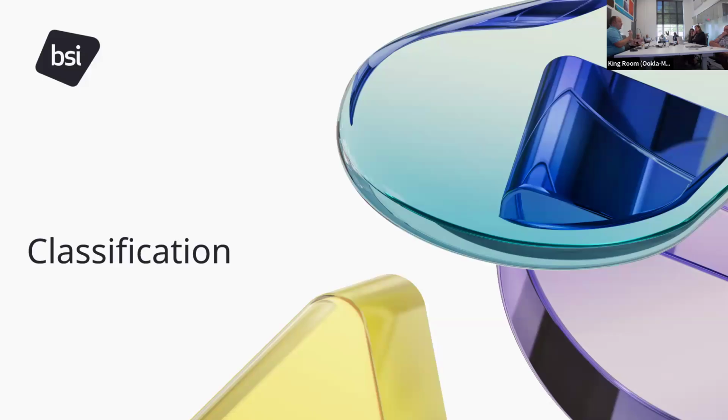So the only thing it does is, after you do the biopsy, you inject these tiny markers into the biopsy cavity so that you can find that biopsy space later if you have a positive diagnosis. So really the only thing it needs to do is not migrate from that site and be visible under imaging. So your clinical performance objectives there would be you can see it and it doesn't migrate. Your safety objectives are it doesn't react adversely with the tissue.